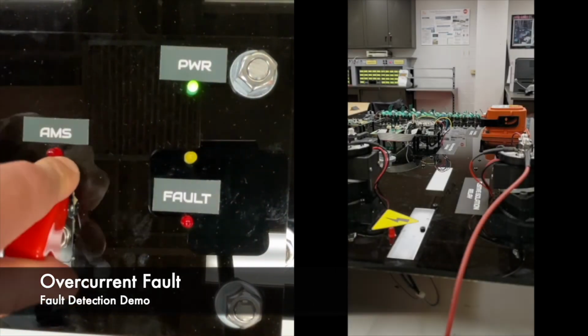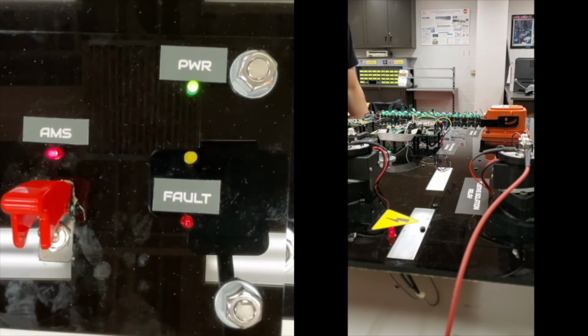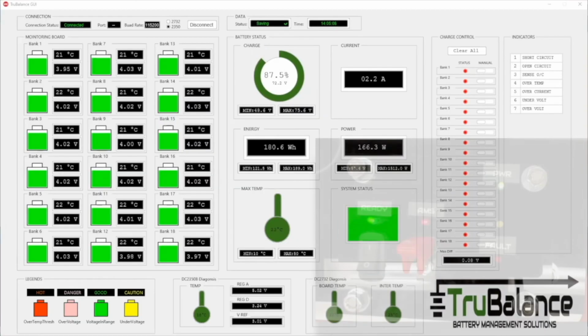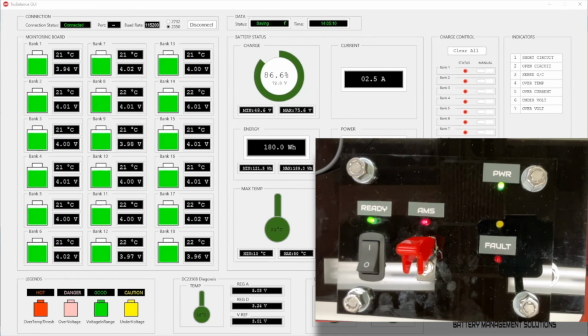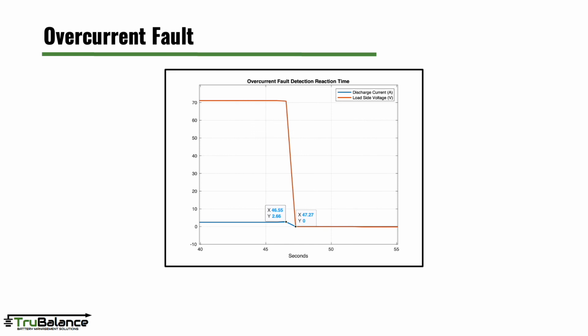When a current higher than our specified maximum is sensed, the system will react by commanding the isolation relays open. In this demo, we have set our current maximum to 2.7 amps. When the current drawn from the battery reaches 2.7 amps or greater, the system opens the isolation relays, illuminates the fault light, and records the fault in the GUI. Our system's fault reaction time, including this demo of an overcurrent condition, occurs in less than 720 milliseconds. That is the time from the moment a fault is detected to when no voltage is present at the load side of the isolation relays.